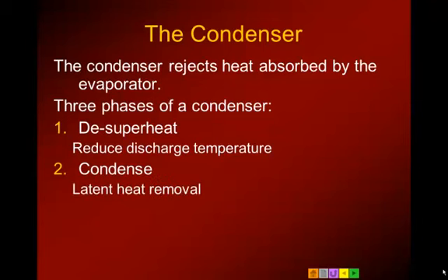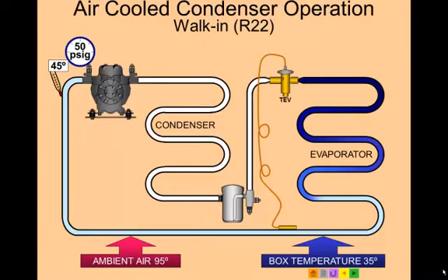Latent heat is removed, so we're going to go through that phase change from vapor to liquid, and then the last few passes of the condenser coil will reduce the temperature below the pressure-temperature relationship, the saturated condition, and that will be sensible cooling, known as subcooling.